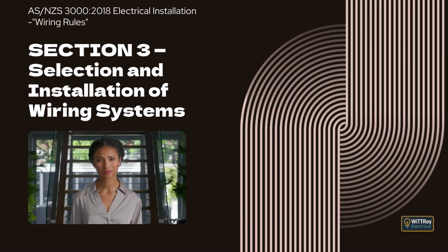Clause 3.7.2.9.1 Joints and connections. This clause explains that joints in aerial conductors under tension must not be soldered, must be reliable and well protected from movement, sunlight, and moisture, and must be kept as short as practicable. Where dissimilar metals are joined, measures must be taken to prevent galvanic action.